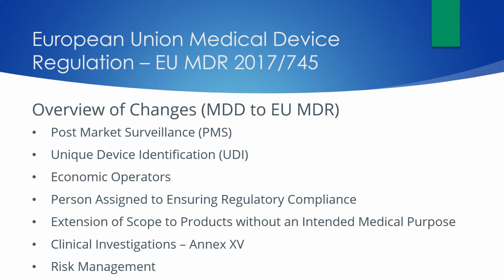The final change that we're going to discuss is around risk management. Each device must have a documented risk management plan. The requirements are very similar to ISO 14971, which means ISO 14971 will be the new minimum standard for device risk management under EU MDR.